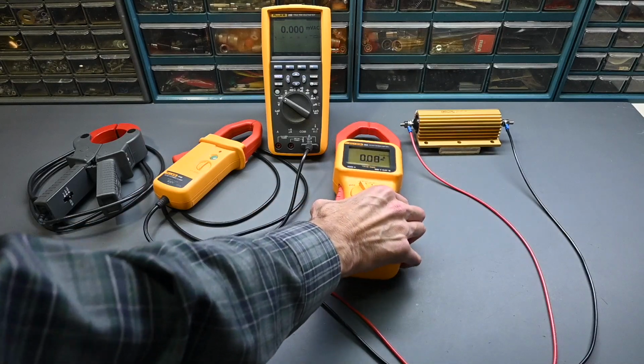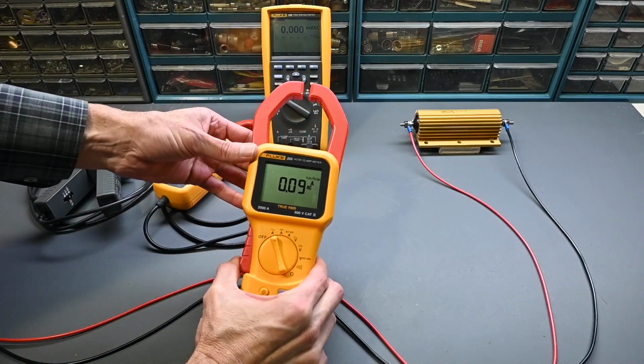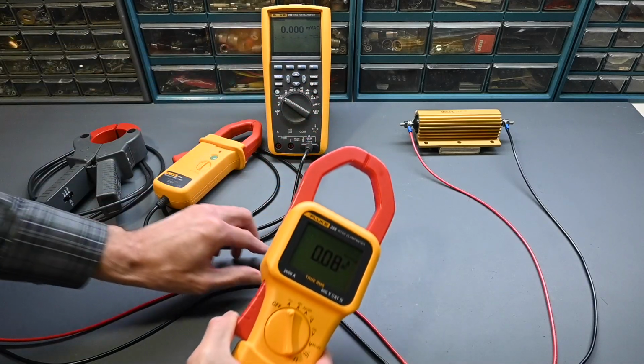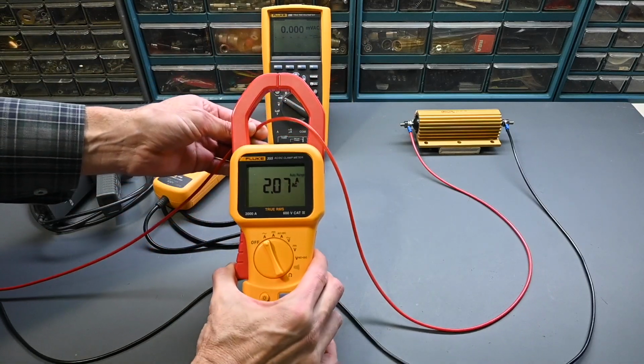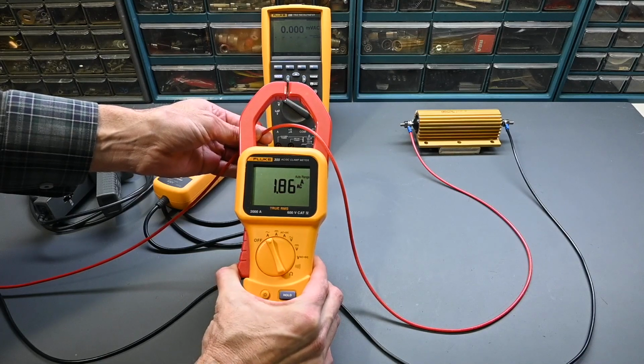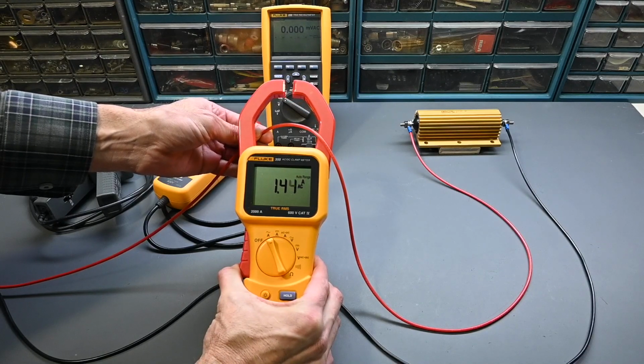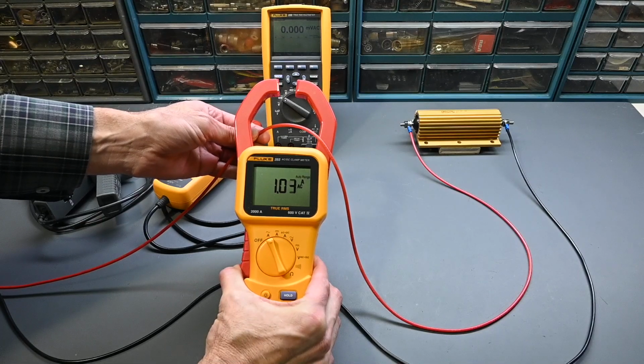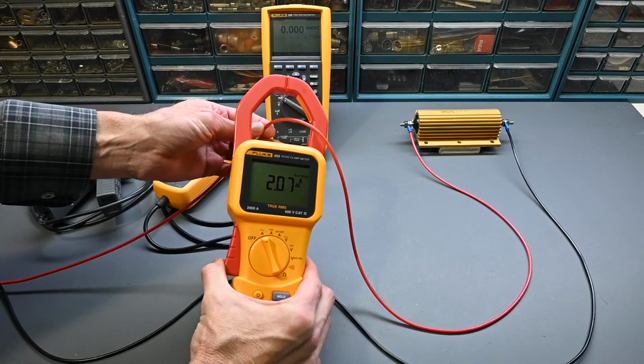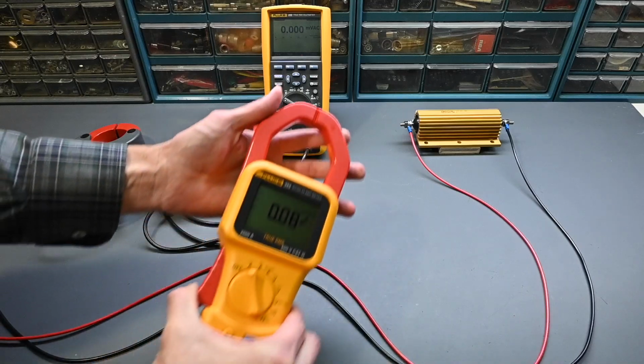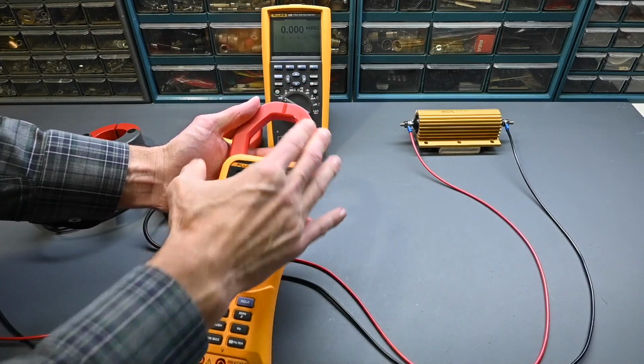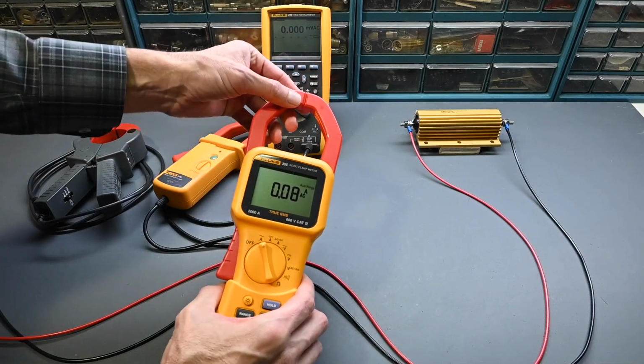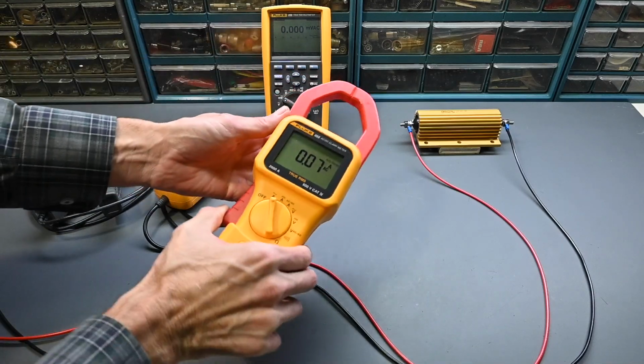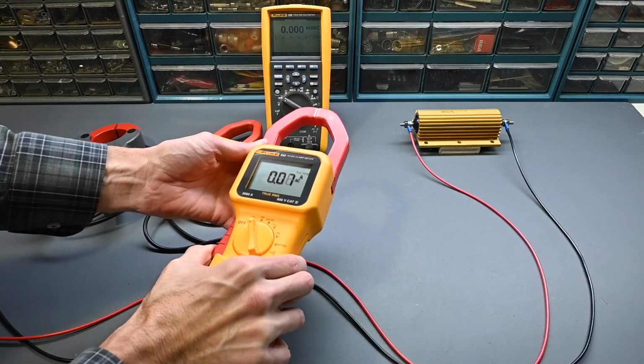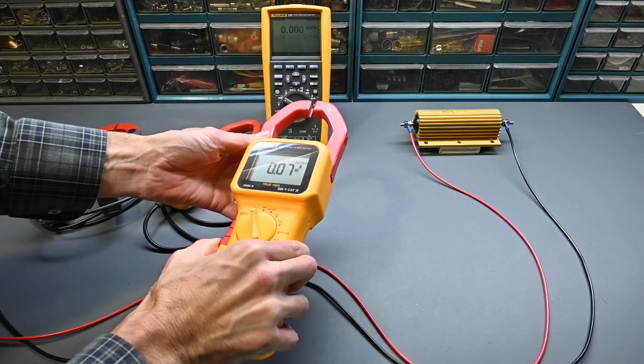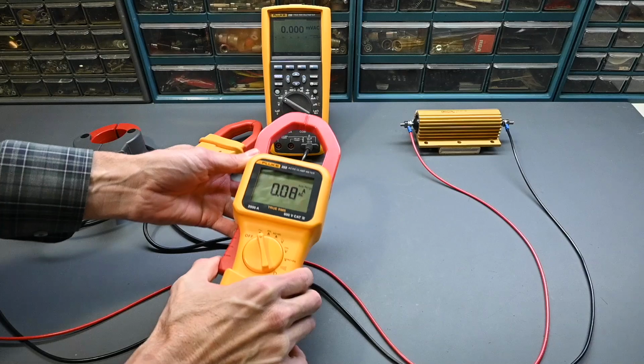Now something else is that when you're taking a measurement, you don't want the current clamp to be apart at all. It has to be completely together. So if I go like this again, and see the 2 amps, but as I start to open up the clamp just the tiniest amount, you can see the current falls away. The numbers are no longer accurate. So it's very important that those be completely closed. That might seem like an obvious thing, but if this is in an awkward position, you're trying to reach in, and the wiring is maybe kind of stiff and you're trying to get the jaws of the clamp around some awkward location, sometimes it can hang up a little bit and they'll be open just slightly, and of course that will affect the reading.